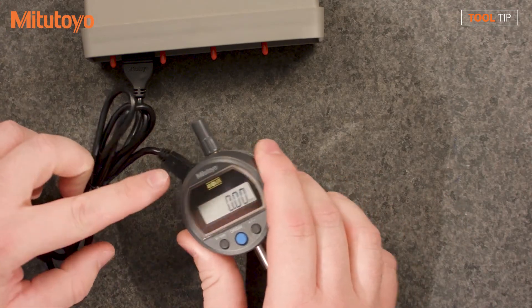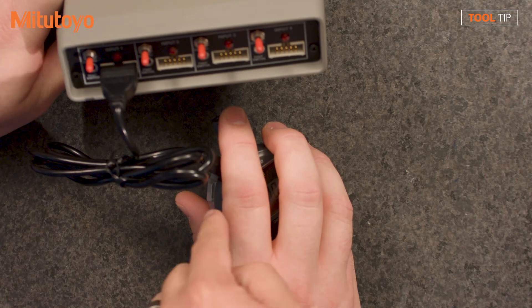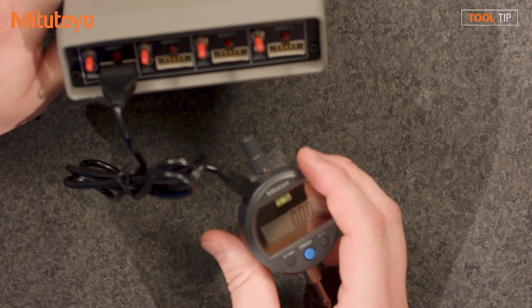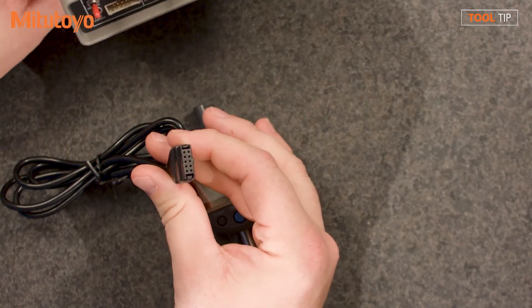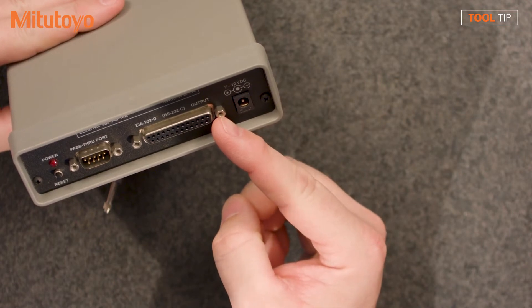A multiplexer is simply a multiple-input device. Same Digimatic connection on the gauge end, but on the other end we're going to use a 10-pin connection to the multiplexer. The cable is a little different — the end plugging into the gauge is still the same, but the other end is a D-type cable, not USB. You plug this into your multiplexer, and on the other end of the MUX is a standard serial port that plugs into your computer.